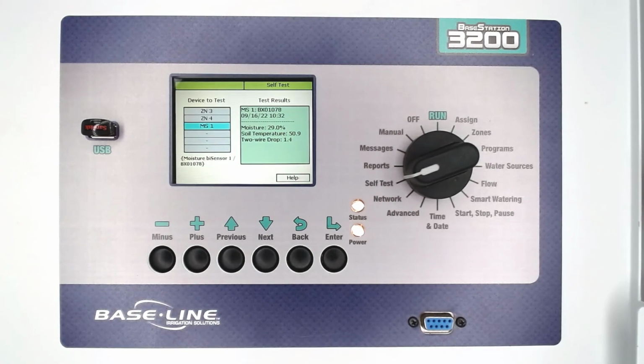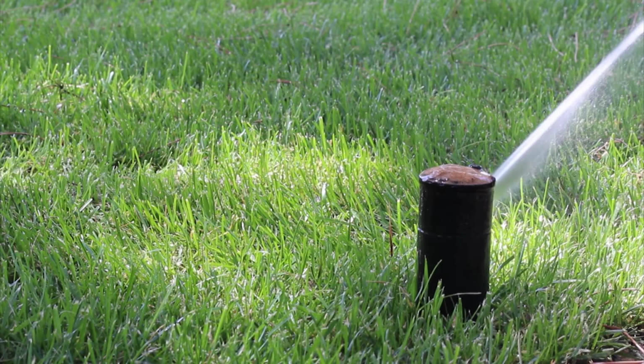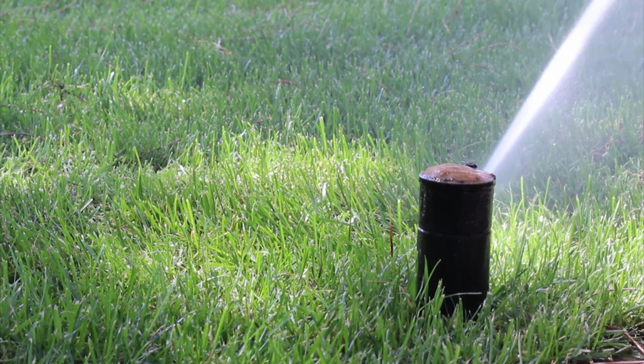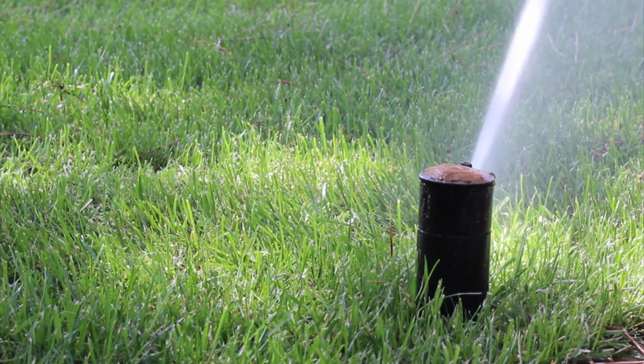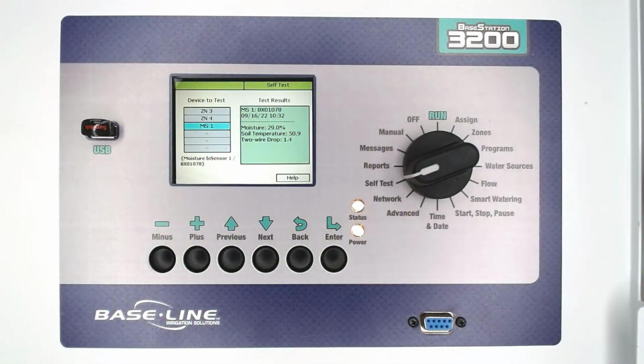Seeing a moisture change means the sensor is working, and I might be trying to wet Moisture Sensor 1 by running a zone where it isn't installed. Look again at the test results. The sensor showed 29% moisture and 50 degrees temperature. This info lets us know that the sensor is communicating with the controller properly. We'll want to look at the sensor installation, the wire, and the wire splices.